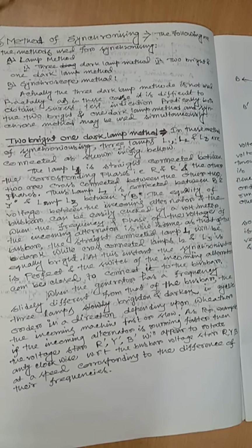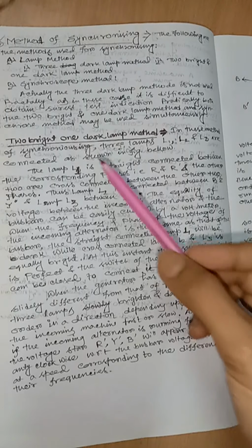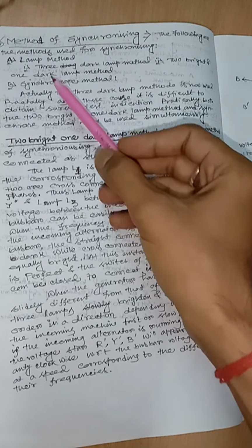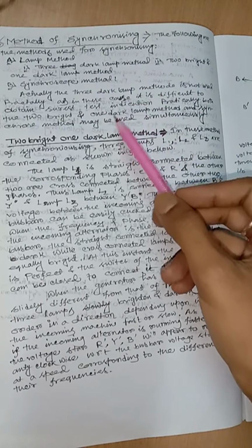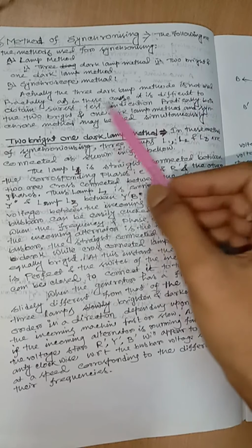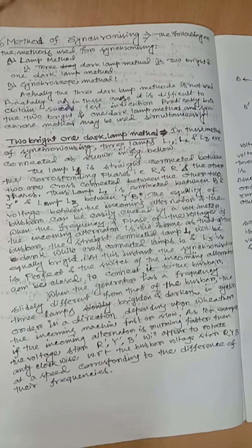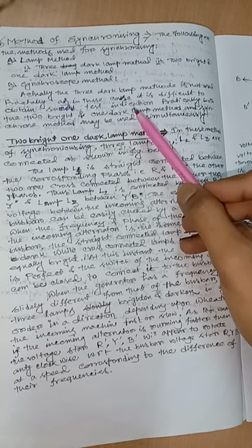Difference in frequency and phase of the voltage of the incoming alternator and bus bar can be checked by one of the following two methods. These methods are number A, lamp method, and number B, synchroscope method. The lamp method is classified in two cases: number 1, three dark lamp method, and number 2, two bright and one dark lamp method. The three dark lamp method is not used practically, as in this case it is difficult to obtain such test indication. Practically, both the two bright and one dark lamp method and the synchroscope method may be used simultaneously.